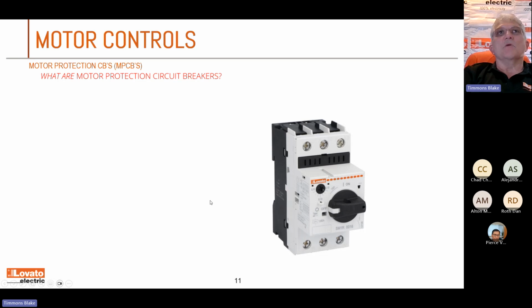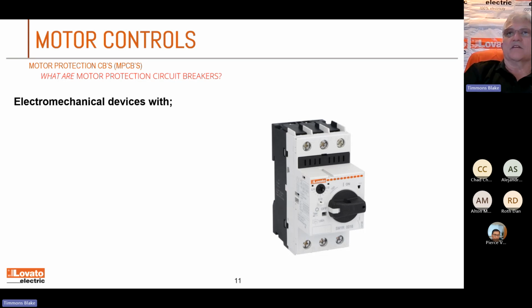Okay, what's next is our motor protection circuit breakers, manual motor protectors, MPCBs. That's what all these terminologies are used for. I've seen people get kind of loose with that and use a lot of other terms, but manual motor protectors is the main thing I see. It's basically the same kind of deal. You don't have any remote control off of it, but you can run your supply leads into the top and your motor leads out the bottom. And you can manually turn that rotary switch off and on, so you've got a bit of a disconnecting means there. If you look just to the left of that big dial, you'll see a current adjustment, so you also have a thermal overload built in.